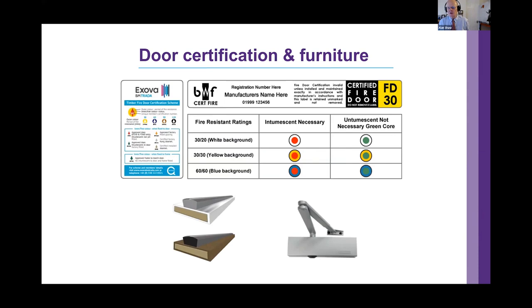This slide is very useful to you. If you've got a camera on your smartphone, take a photograph of it. That gives you the necessary background information on markings that you may find on fire door furniture. Fire door certification is a big issue and it includes the hardware and ironmongery, including the smoke seals, the intumescent strips, and the self-closers — or the hold-openers, as I call them.